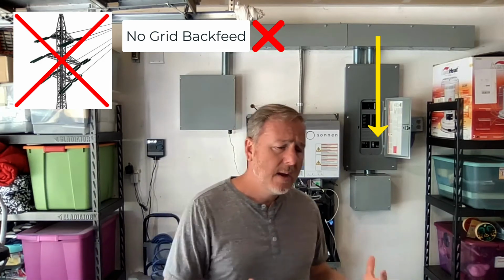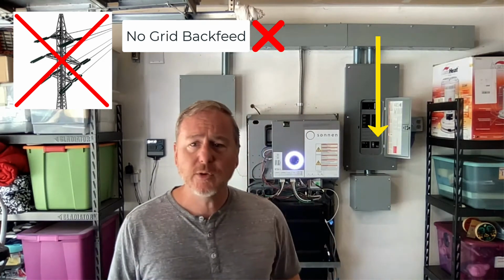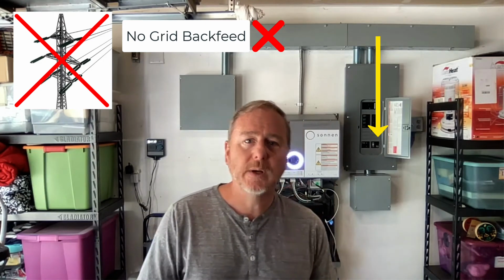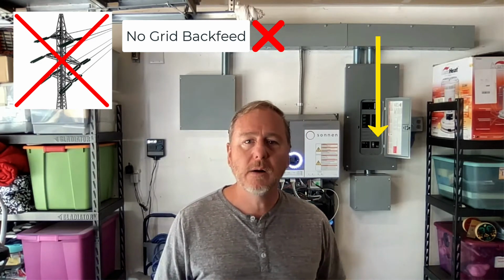Now, some battery manufacturers have these things called dump loads, where it'll turn on something like a hot water heater somewhere to send those electrons. Usually it's to a heating element, because that will suck up any extra electrons. But if you don't have that, which a lot of manufacturers don't, then what we have to do is throttle the solar down, right? Because we don't have anywhere for that excess solar to go. We don't want to overcharge the batteries.